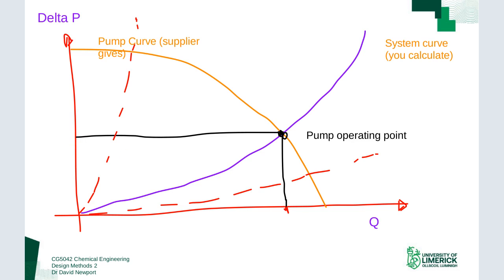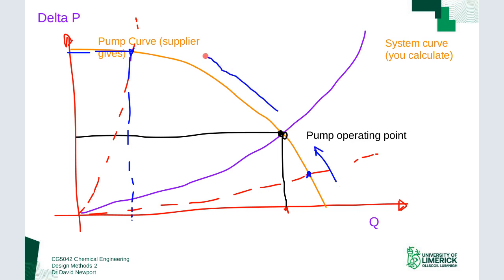If we had a high-pressure system, our operating point would be higher up — much harder to push the fluid through, giving a higher pressure drop and much lower flow rate. For the low-pressure system, the operating point shifts down. So you shift depending on the system — you move along the pump curve as the system changes, and that intersection point moves through various locations.